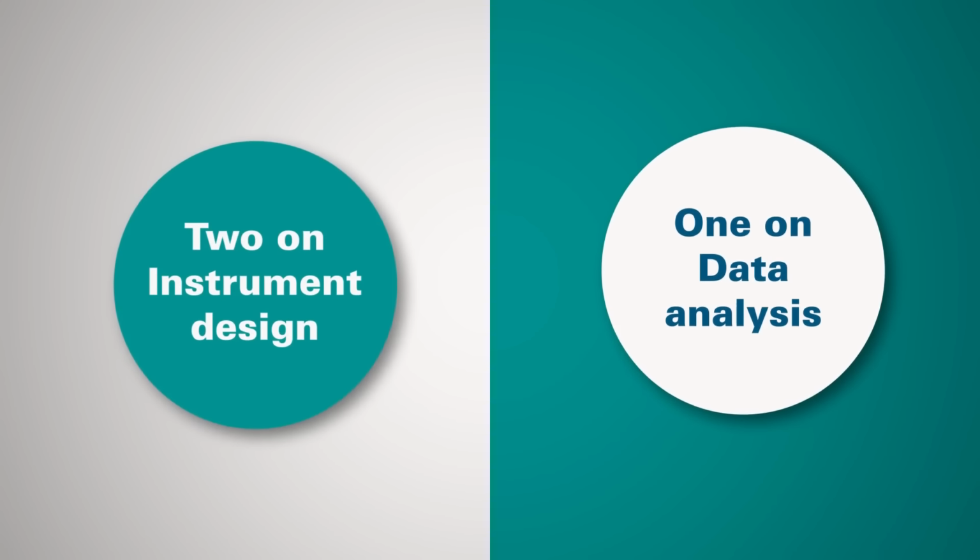For our instrument, we have three innovations on the multi-angle light scattering technique: two on the instrument design and one on the data analysis. The first one is a patented flow cell design. This flow cell is made of PEEK, which is a bioinert material.